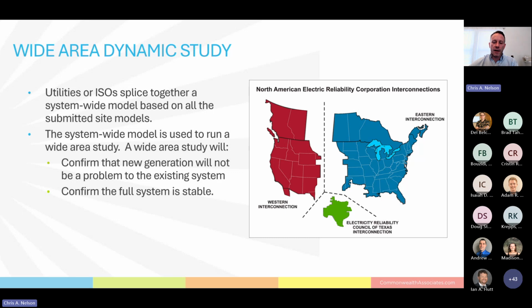They'll have the entire interconnection of MISO mapped out in the model, but they'll only run faults near a newly connected generator just to make sure that generator works. Because even if the generator works on a small site, it might not behave perfectly in the larger model. So that's what they want to run and find out, just to make sure all the generators behave together instead of just by themselves.